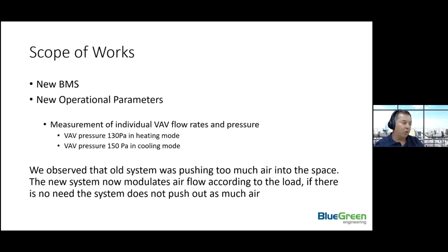The scope of works that we wrote up proposed a new BMS system with new operational parameters. And one of the operational parameters was to reduce the pressure and the flow rate on the VAV boxes, which regulate the volume flow. In doing this, we observed that the old system was pushing too much air into the space, and the new system catered for the building's needs and modulated the flow according to the load. So if there was no need, the system would reduce the pressure even lower.